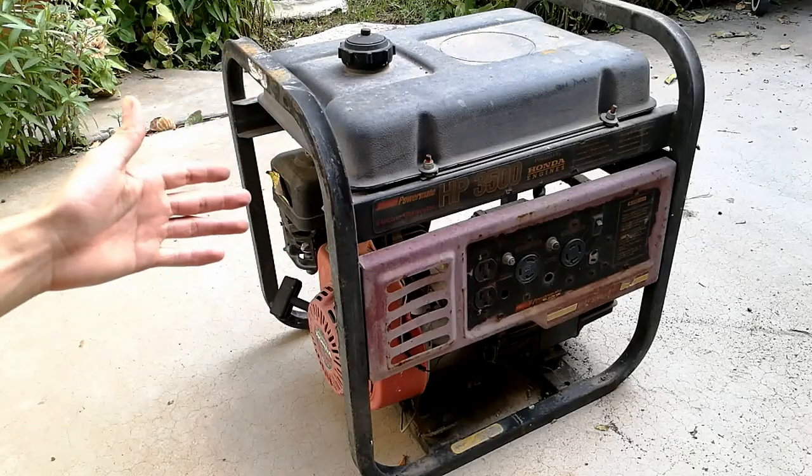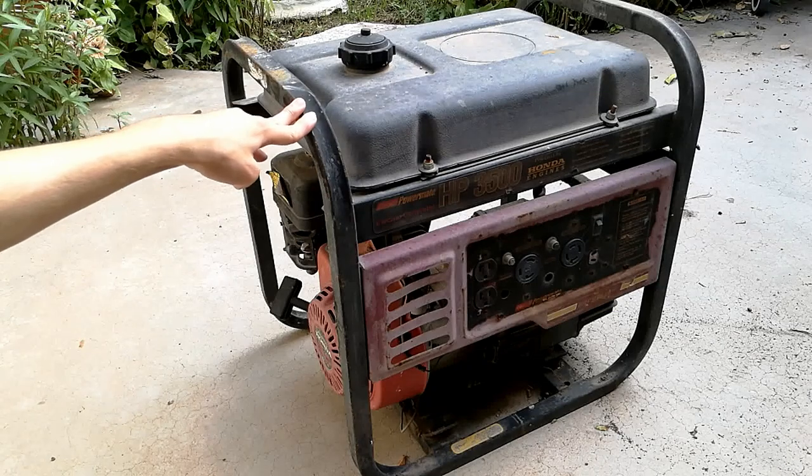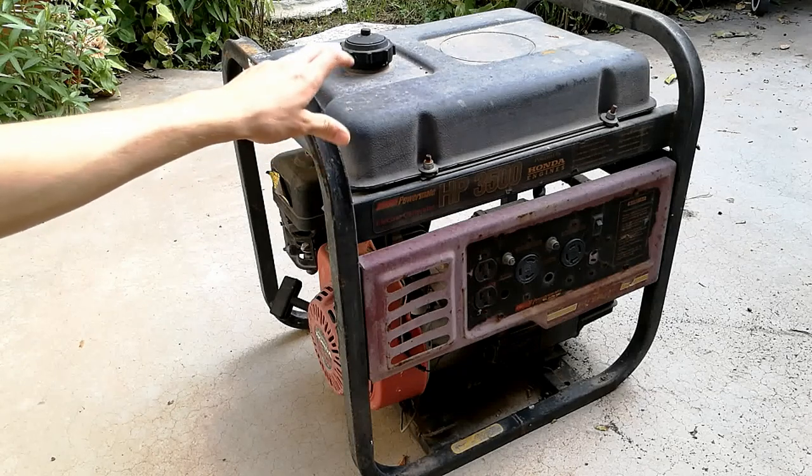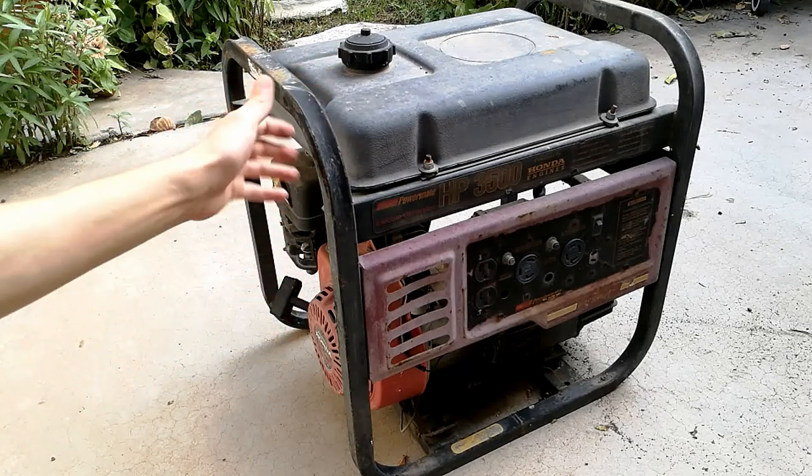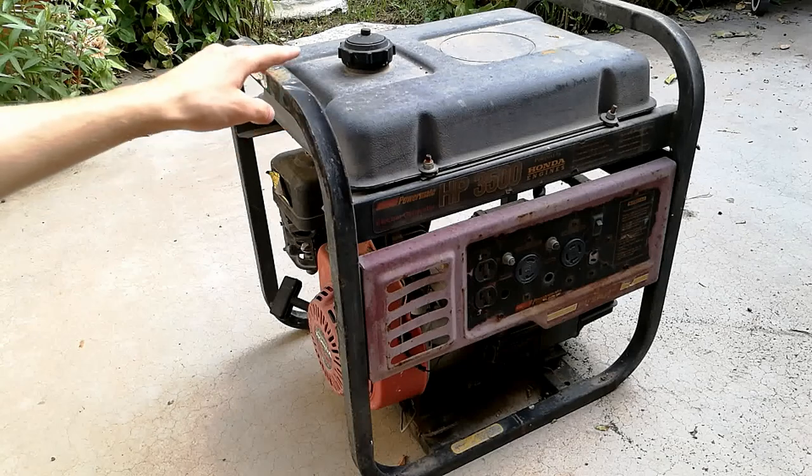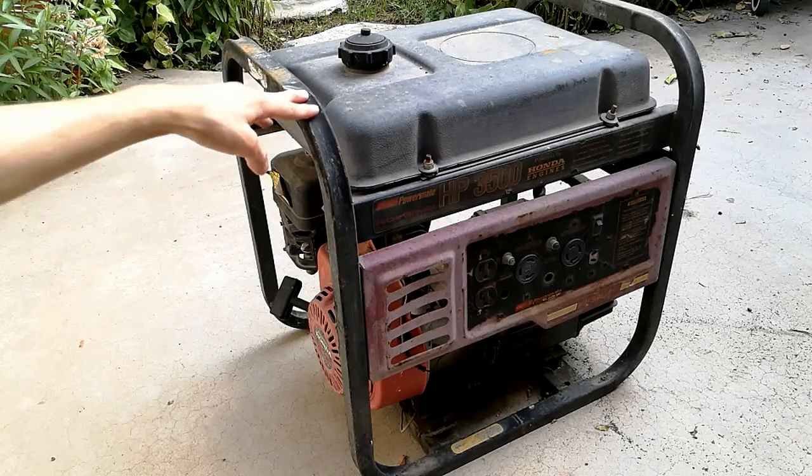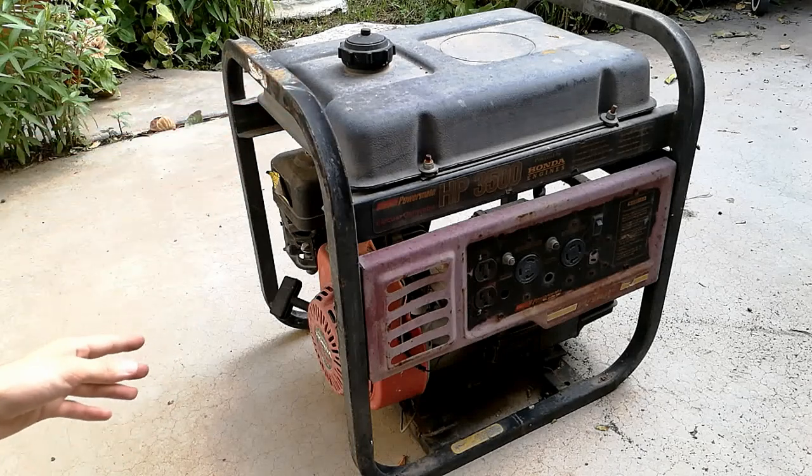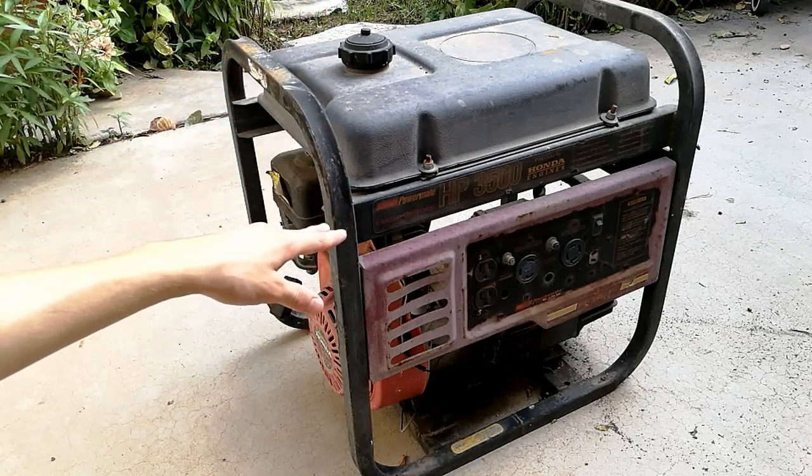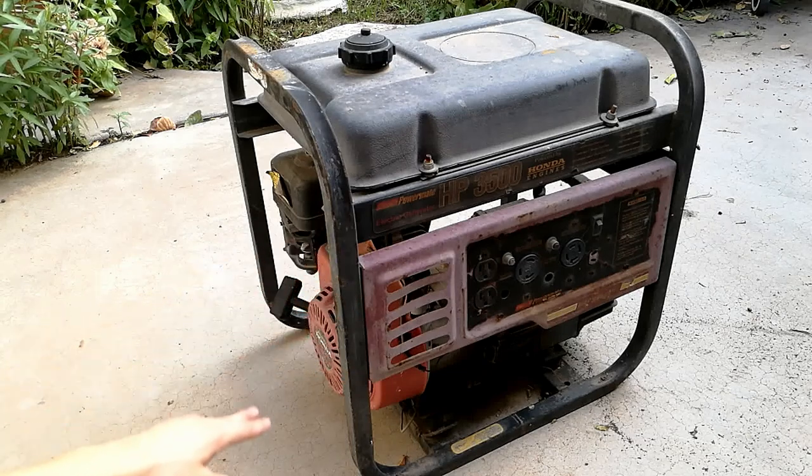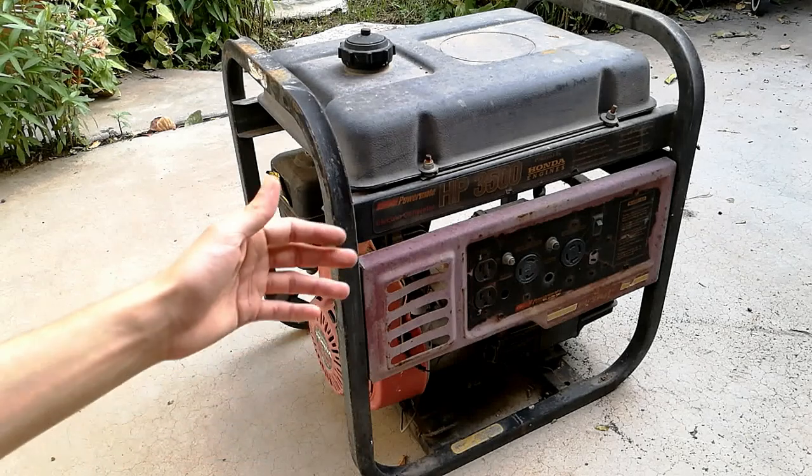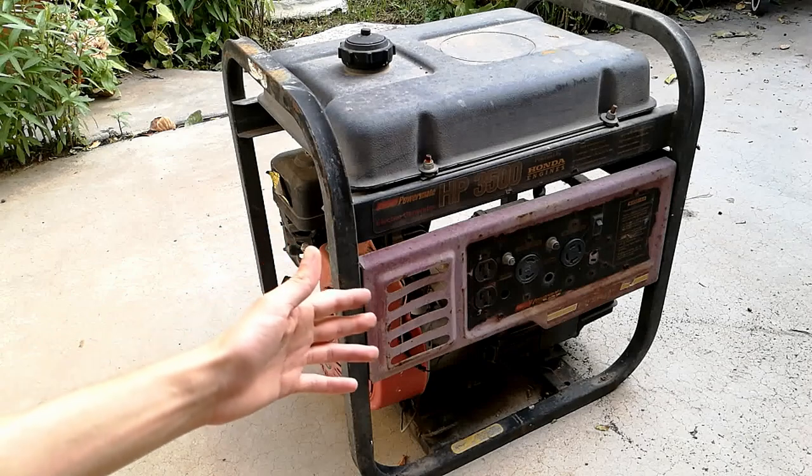Here's a reason why you might want to know about what effects low quality power has on switched mode power supplies. This is an old-fashioned 3500 watt electric generator with a gas engine on it and this is important to note because this is not an inverter generator. This is a direct driven alternator meaning that all voltage and frequency regulation at the output as well as voltage stability are completely at the whim of the engine. If the engine revs, if the RPM increases, then the voltage and frequency will also increase proportionately. If the engine bogs down, the voltage and frequency will drop.